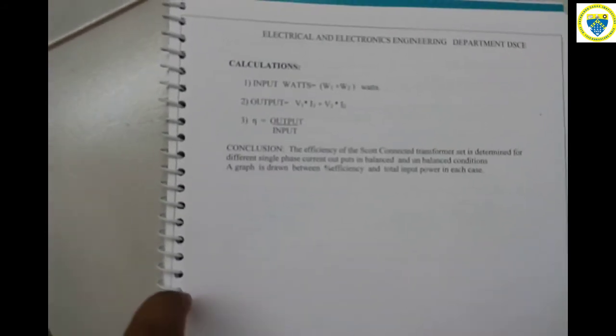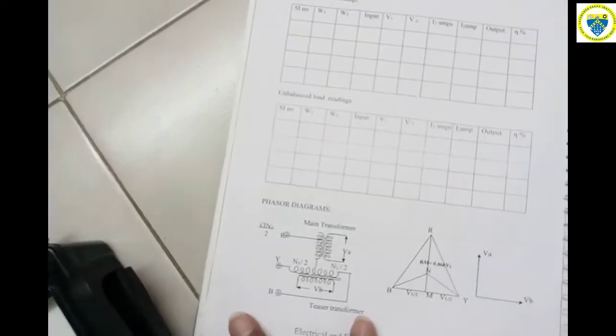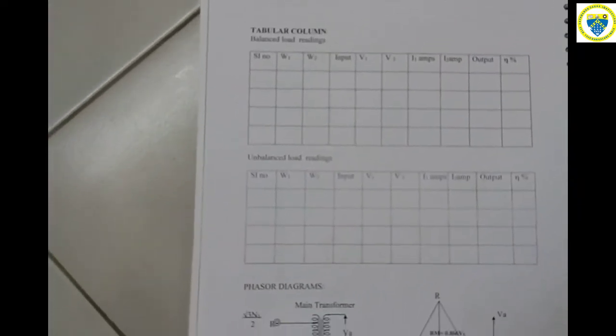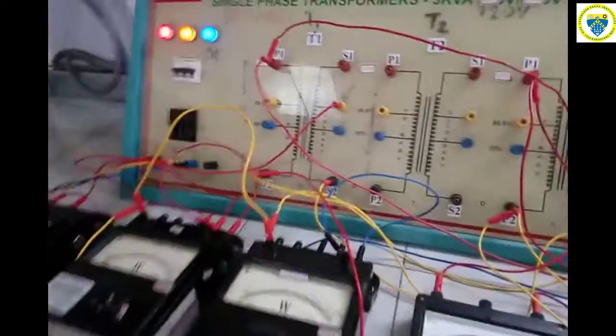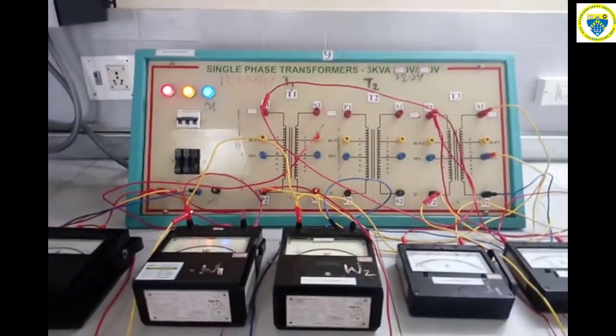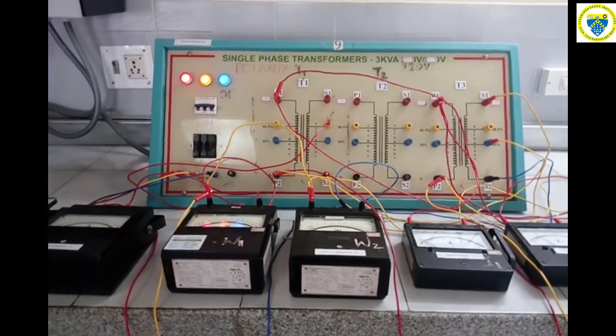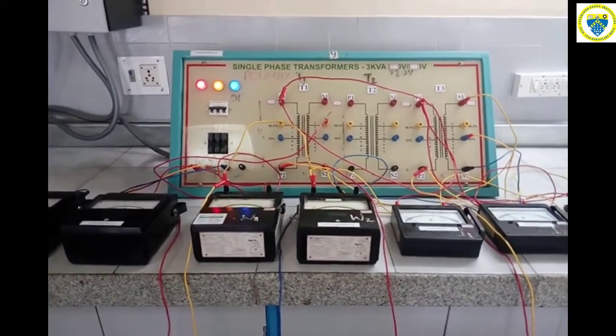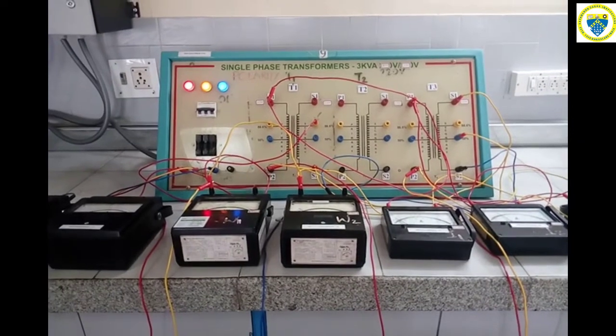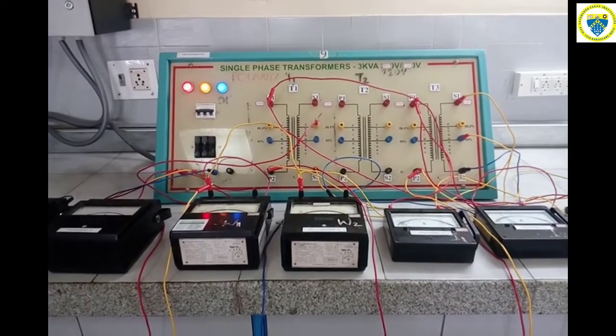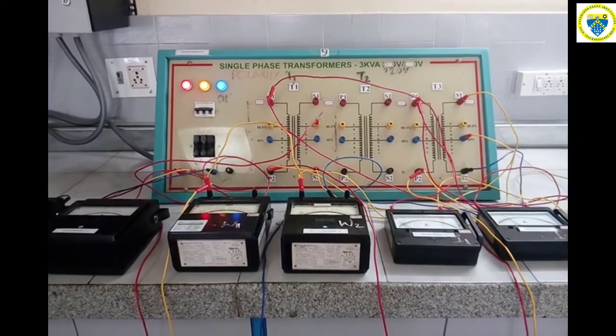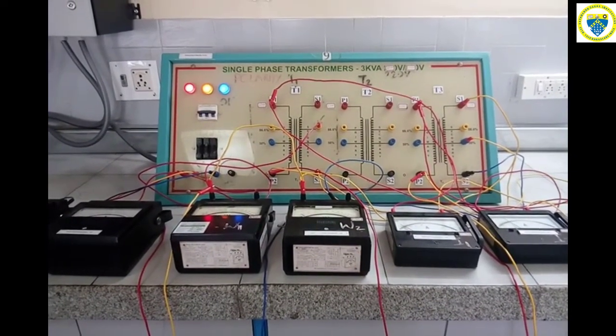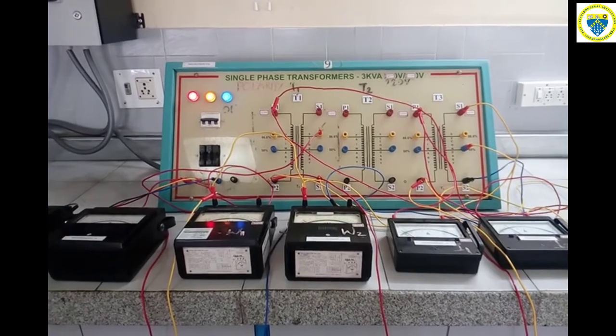And finally, the calculations are made by using the formulas provided in the manual. Then the efficiency of the transformer for balanced as well as unbalanced load is calculated. The main intention of conducting this experiment is to convert a 3-phase supply into 2 single-phase supplies, and 2 single-phase supplies are helpful in furnaces for heating up iron ores. So this completes the SCOTT connection on a 3-phase transformer.